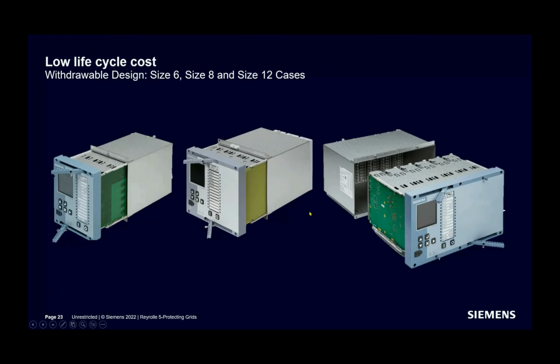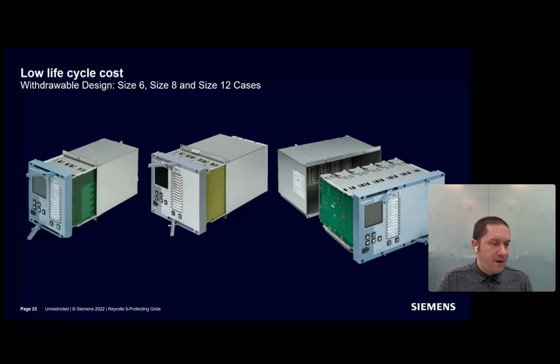Now, sorry for this ugly slide, but it is the fact. Now, a key feature of the Reyrolle 5, which is common throughout the Reyrolle brand, is the ability to easily remove the device from its case without disturbing the wiring and shorting the CT secondary terminals. So this allows quick and easy, safe installation and removal of devices, enabling a fast product replacement in service.